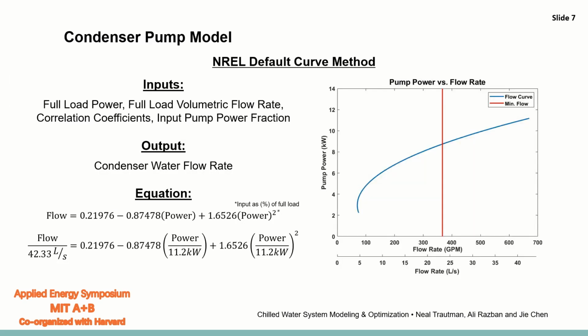So for our condenser pump model, we use the NREL default curve method, which uses data collected at full load power from the condenser water pump and full load volumetric flow rate from the Fuji ultrasonic flow meter, as well as correlation coefficients provided by NREL in order to determine the flow rate as a relationship to an input power fraction. The relationship can be seen in the bottom left under equation. Once we input our full load values, we were able to develop the graph to our right. The red line on the graph to the right indicates the minimum flow rate that's allowed through the chiller in order to maintain turbulent flow on the condenser side of the chiller.